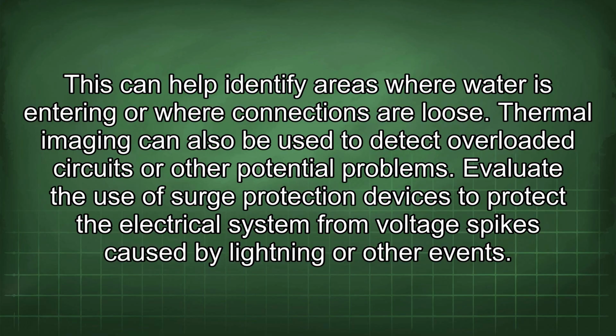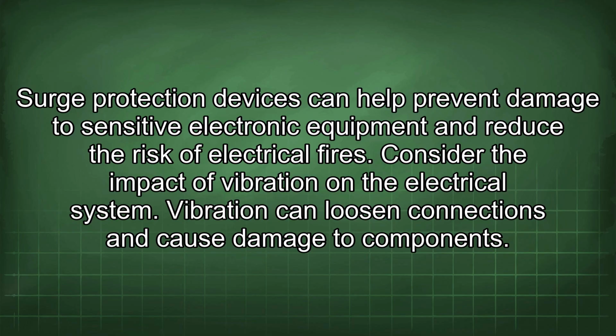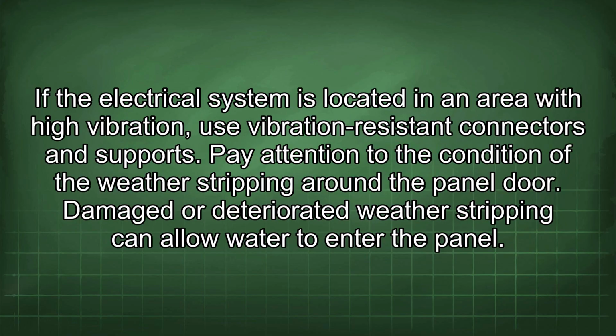Evaluate the use of surge protection devices to protect the electrical system from voltage spikes caused by lightning or other events. Surge protection devices can help prevent damage to sensitive electronic equipment and reduce the risk of electrical fires. Consider the impact of vibration on the electrical system. Vibration can loosen connections and cause damage to components. If the electrical system is located in an area with high vibration, use vibration-resistant connectors and supports.